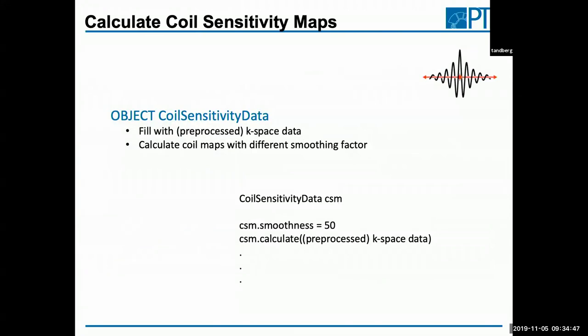In SIRF, a method for calculating coil sensitivities is implemented. There is an object called CoilSensitivityData — you put K-space data in and call an option to calculate coil maps. You can set parameters such as a smoothness constraint to ensure spatially smooth coil maps. It's basically just two or three lines of code to get your coil maps.